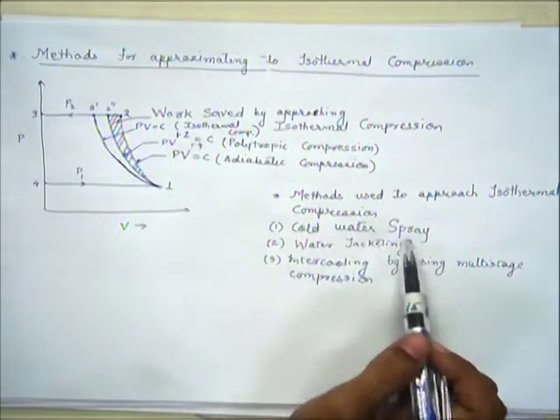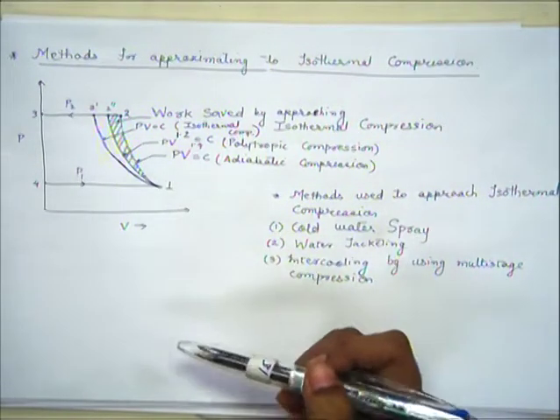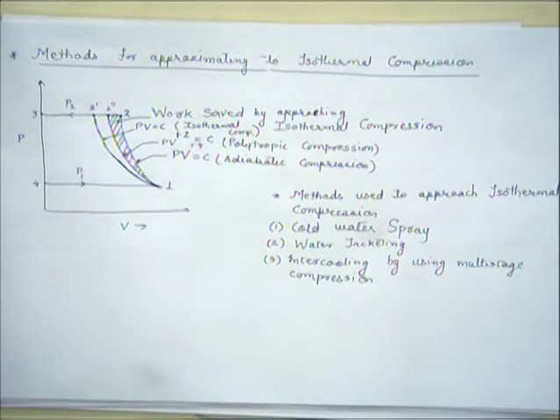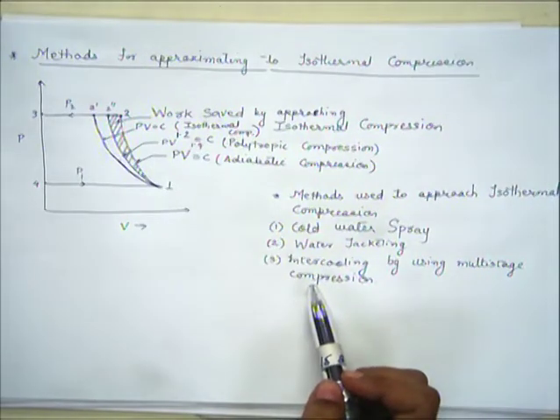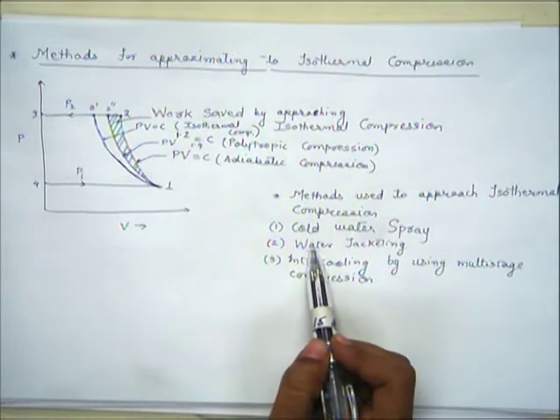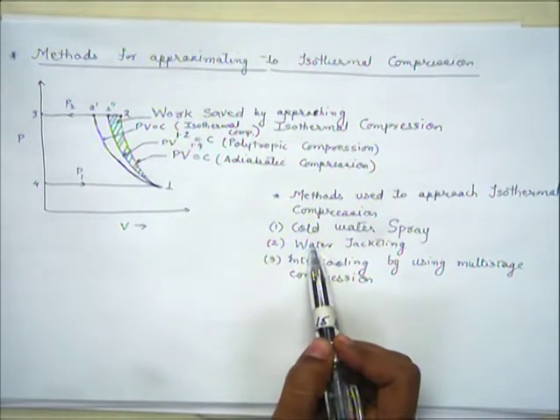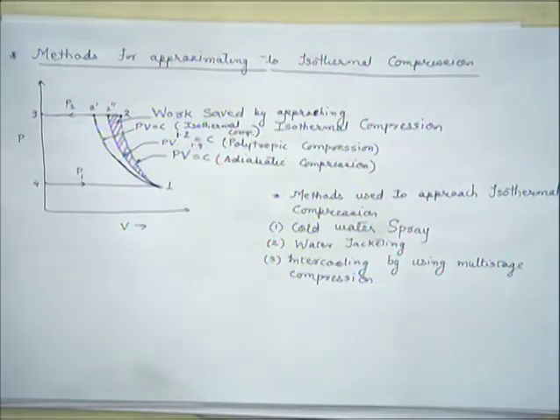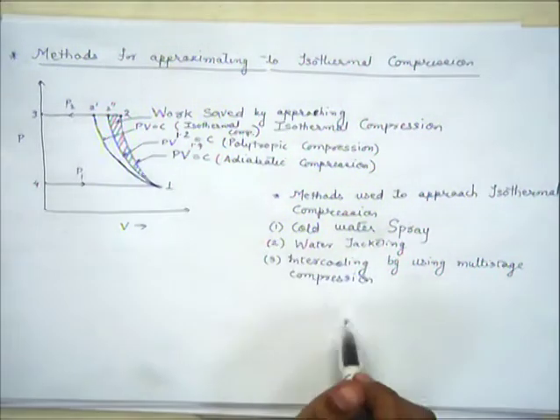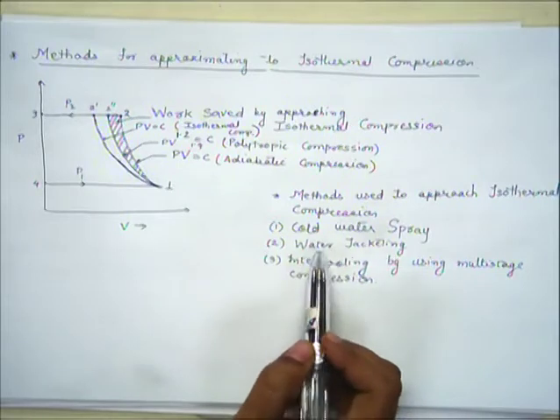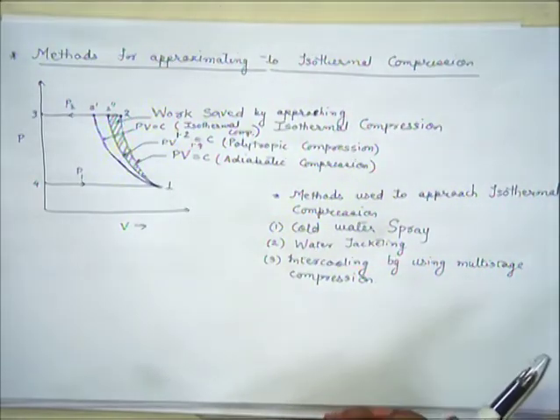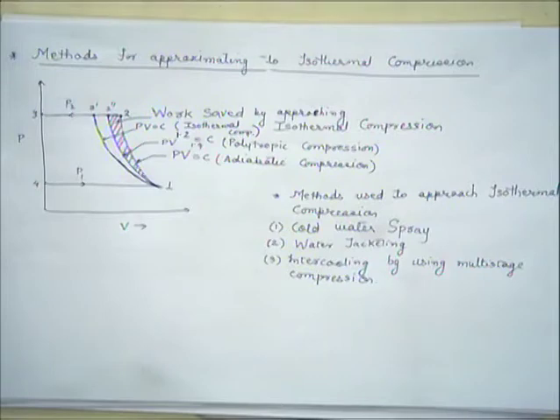One method for approximating isothermal compression is cold water spray — we spray cold water on the outer side of the cylinder, thereby cooling the air within. A second method is water jacketing, where a water jacket surrounds the cylinder and cold water circulates continuously, with cold water going in and hot water coming out to cool the cylinder. A third method is intercooling using multi-stage compression.